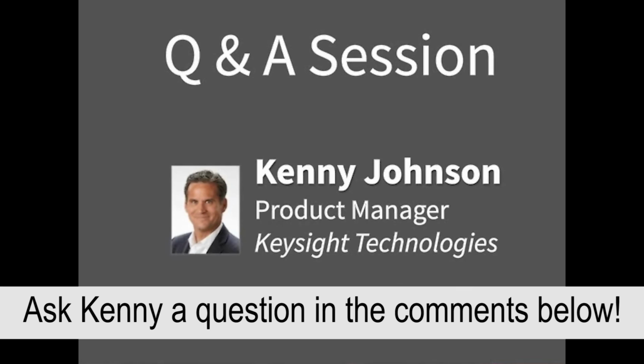Yeah, I know. Kind of like with my car, it's like, am I still getting the same gas mileage or horsepower out of this? I wish my car came with what we call a PV procedure, and that's exactly what it is. We've got performance verification procedures that we publish in the user's guide for our probes. What it does is take the key important characteristics or specifications and tell you how you can go verify those.